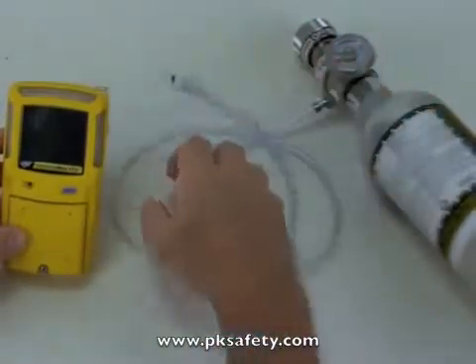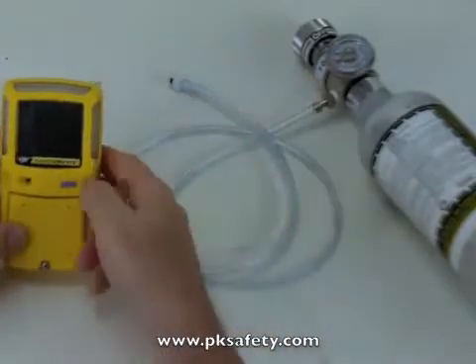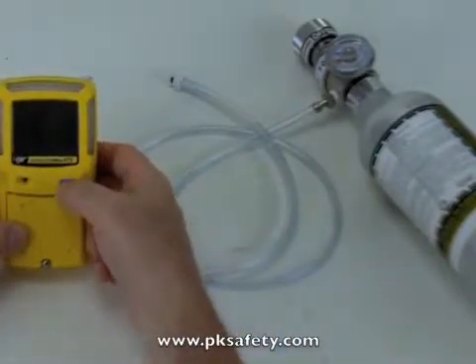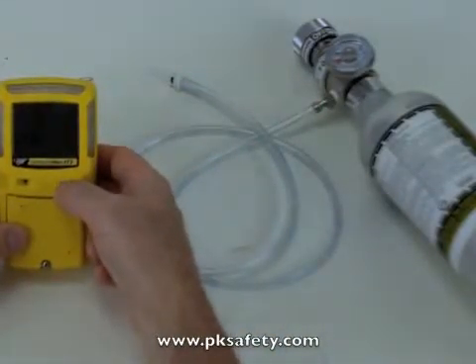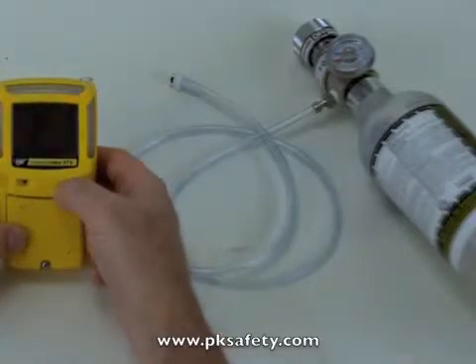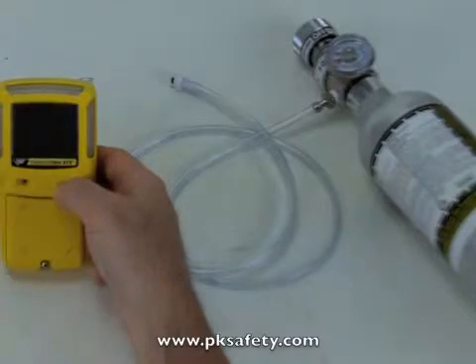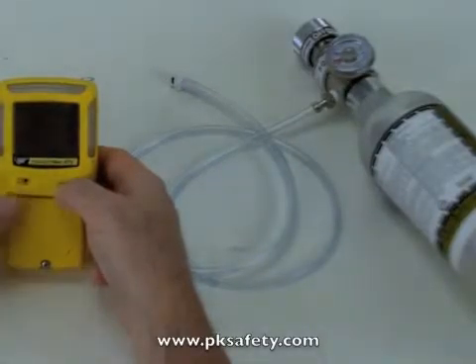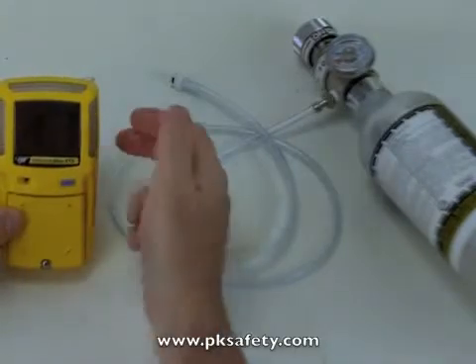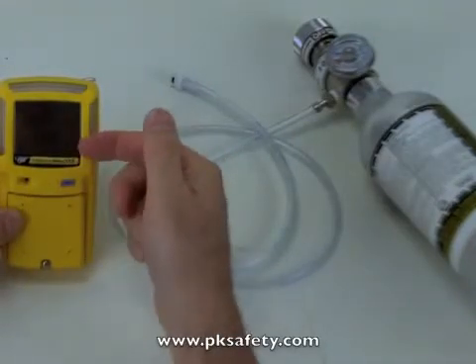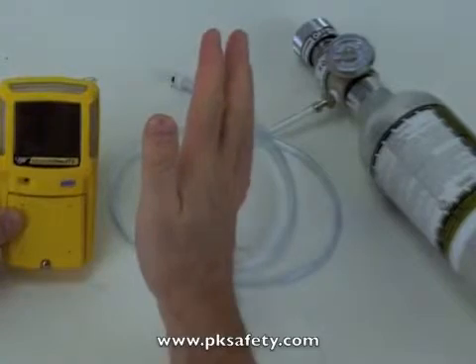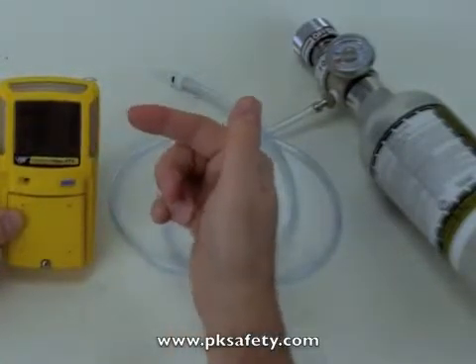So first thing that I'm going to do, now that I'm ready to go, I've got everything here, is I'm going to press this button. It's important when you're doing this, you press and hold this button. So I'm going to press it in and hold it. And it's counting down off 3, 2, 1. The screen goes blank, but then it comes back up with cal in 1, 2, 3. Now I can release this, and it's auto-zeroing. Important that we do this in an area of clean air. And now it says apply gas.